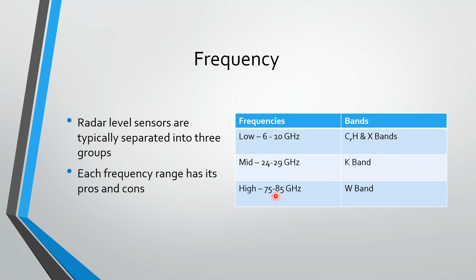So what are the pros and cons of each frequency group? Remember, antennas and all that stuff will also affect this, but this is just some basic pros and cons. If we're looking at our lower frequency non-contact radar devices, when it comes to condensation, foam, vapor, and dust, they're the ones that are going to have the least amount of problems. Depending upon the antenna type, they may also have the least amount of problems with buildup on the antenna. These are the ones that are least affected by waves or ripples. They tend to have a larger beam, so they will average out those waves or ripples much better than something with a narrower beam, which would be a higher frequency device.